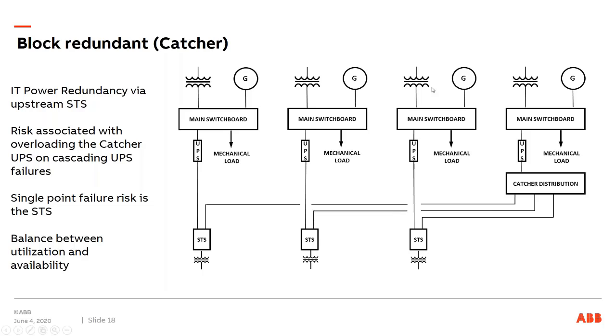But this one is just showing 4 systems, each with 3 main UPSs and a catcher UPS. Each main UPS is feeding its own load. And the catcher UPS is just sitting idle, not really doing anything, except sitting there ready to take over. So if something happens to UPS number 1, the static transfer switch will automatically transfer the load to the catcher UPS. The benefit with this is that we have 4 UPSs, but we can load 3 of them up to 100%. So now we increase the utilization up to 75%.